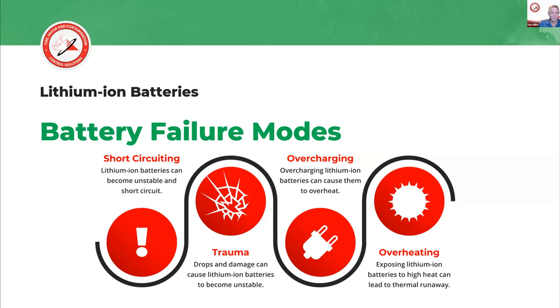Overcharging is another failure mode. Overcharging a lithium-ion battery causes it to overheat. This happens a couple of different ways. Number one, it could be a higher voltage than the battery is rated for, due to someone using a charger that's not designed for the battery equipment being charged. Maybe they bought an illegitimate charger, or one that's homemade or modified, and they're charging at too high a voltage than the batteries were meant for.